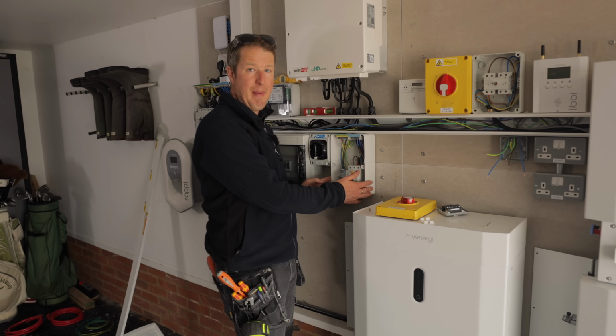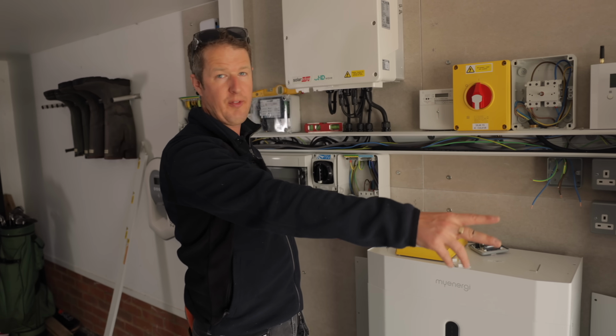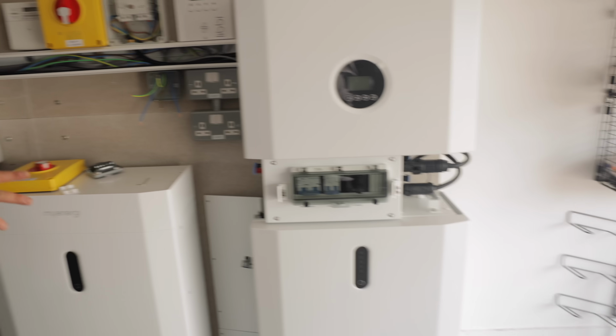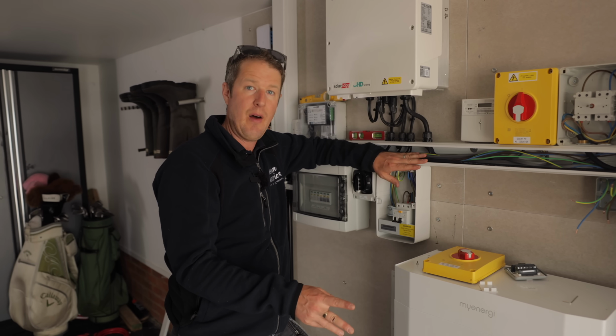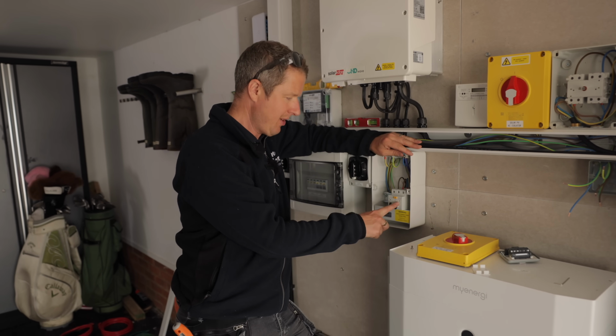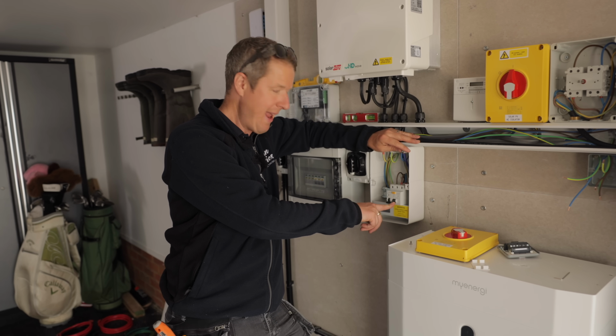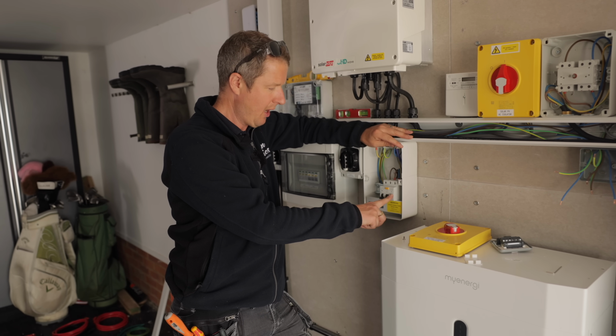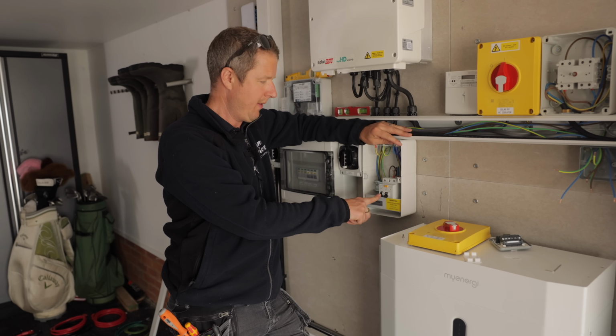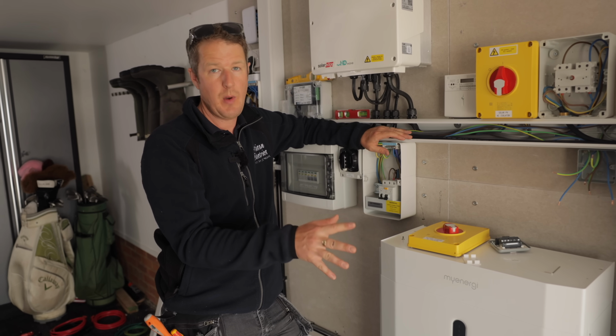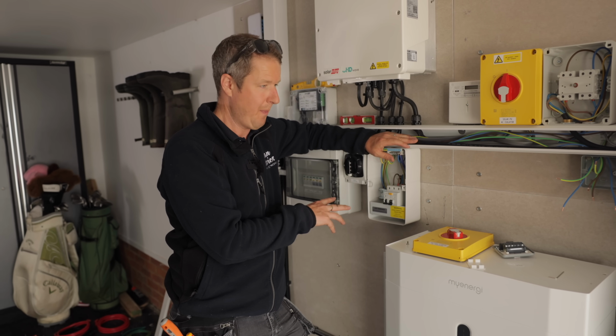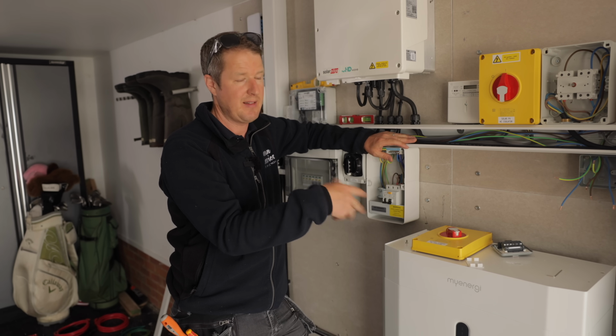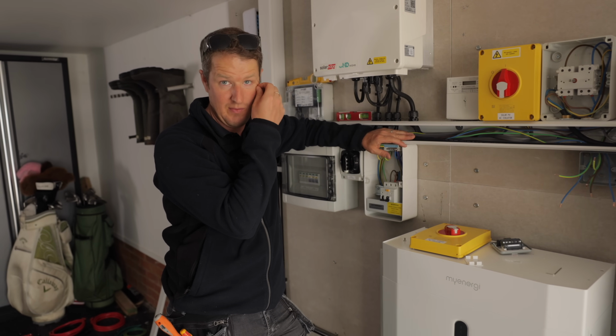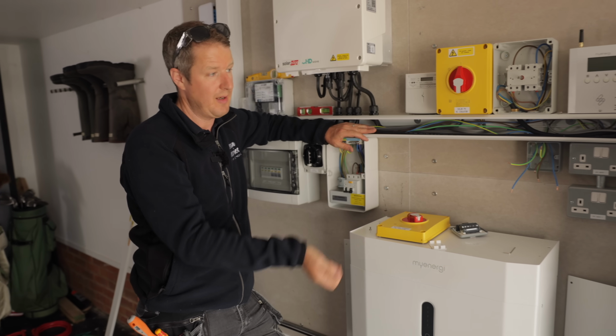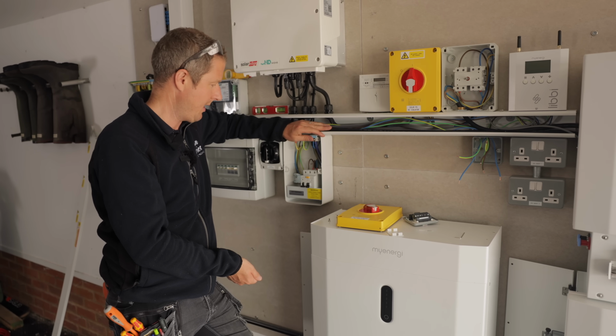So we've installed this backup consumer unit here, wired off the backup terminal of the Libbi. Now there's a few rules about backup power that you need to be careful of. The backup circuits must be protected by type A RCD. So that's what we've done, type A RCD here with an MCB. Now in this case we're only running 2 double sockets off the backup circuit. They're just there as emergency power supply in case of a loss of power from the grid, that the customer's still got a couple of sockets that they can use.